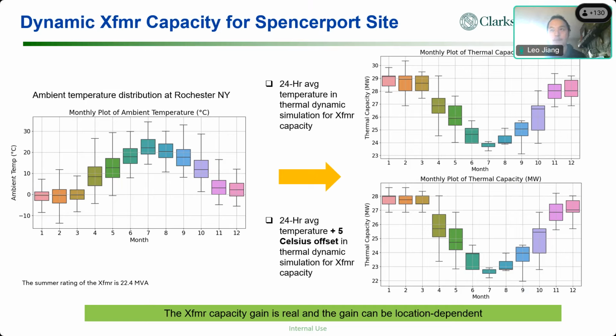And then, as Zach talked about in the flexible interconnection demonstration project, almost all of the curtailment happens in the shoulder months, which are March, April, May, and September, October. If you look at those months, the ambient temperature is not that low, but definitely lower than the 30 degrees, which is the rated ambient temperature for the thermal capacity of the asset. This case is the transformer.